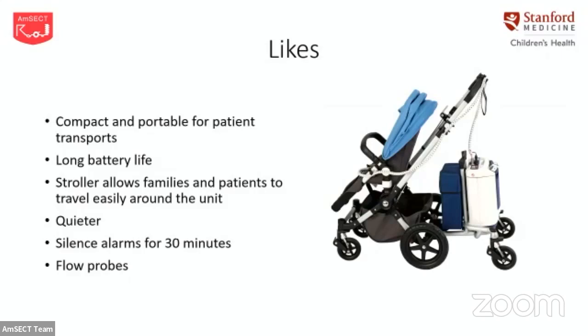We also do the flow probe. Previously, we would do slow-mo and look at how much the pump is filling and say, okay, maybe it's 90%. Based on this pump size and this rate, that's probably this flow. But now you have a flow sensor that tells you what flow you're giving to the patient. And it's also nice to have that alert right away when inadequate support is detected.